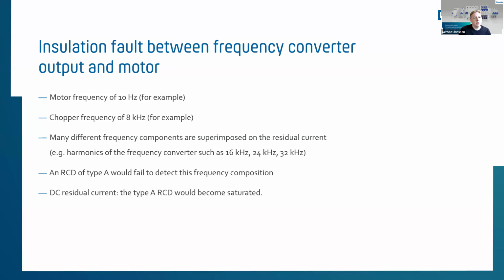So, as told, an RCD of type A would not detect this frequency composition anymore, and the DC part of the residual current would saturate the electromechanical tripping relay in an A-type RCD, would saturate it magnetically, so that the type A would not detect anything anymore. So the type A RCD would be blinded by those DC parts of the residual currents, and it would just stay on. So the whole system would look like it is okay, but it would not detect anything anymore. Even A-type or AC-type residual currents would not be detected anymore when the core of that tripping relay is magnetically saturated.